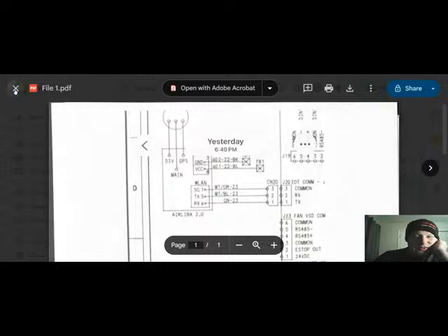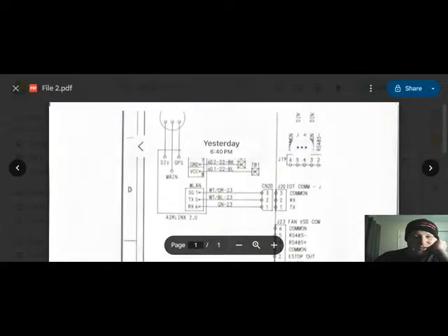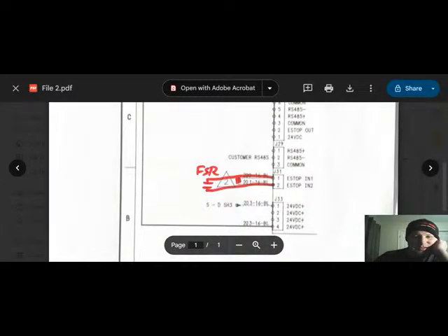And so again, we're going to work through this as a basic function here. So we have what I would call a fire suppression relay, and this is going to be supplied to us by the company that does the fire suppression system. And if it's me, I'm going to ask for a relay that is normally open and closes on energized, and I want this relay to be normally energized.